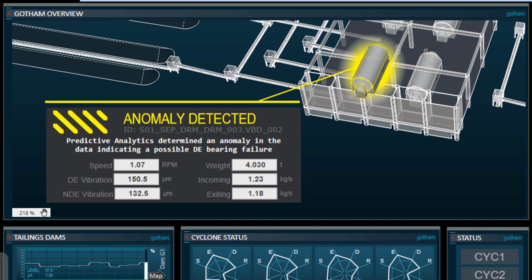and Prism will look at all the measured values on a specific device. So on the drum, it's measuring the speeds, the vibrations, temperatures, weights, and even the sounds. It then determines the relationships between these values during the normal operation modes of a healthy drum. When it detects anomalies in these values or in their relationships, it will notify the viewer of these anomalies and potential problems, even if it hasn't seen a problem before.